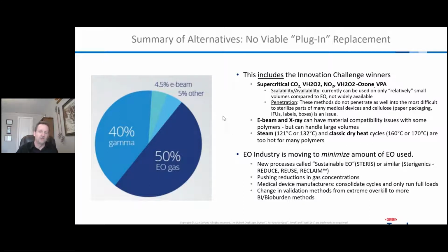The industry is moving to minimize the amount of ethylene oxide that's used, changing in some cases the way the validations are done, so you're not doing this huge amount of overkill, which maybe gave you an 8-hour cycle years ago when you validated, when maybe that cycle really only needs to be an hour and a half or an hour. A lot of companies just didn't take the time to optimize that. It was really faster just to pick a time. I'm going to pick 4 hours. Yep, 4 hours worked, and I can go on and get this validation done and put it behind me. But they didn't go back to say, maybe we could have done this in 1 hour, or maybe we could have cut the gas concentration in half.